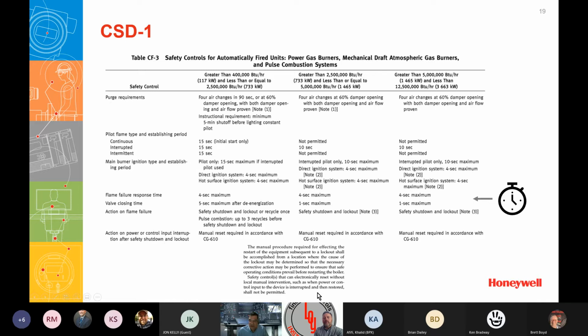You could ignore it, but then again, if you look at the performance standards like IEC 61508, it actually states something like this: no one can inadvertently allow gas flow to a furnace or heater without the burner management system being in control. It's kind of how they capture it, and that's when they get into the discussion of manual latching reset mechanisms, of which I'm going to explain how that works.